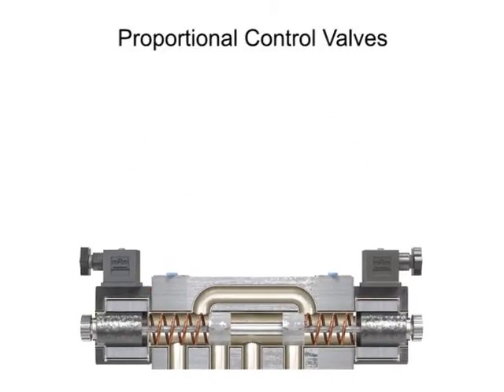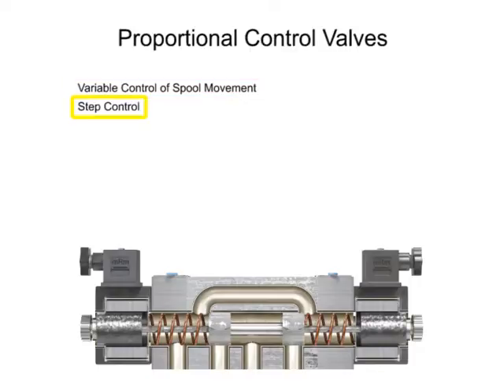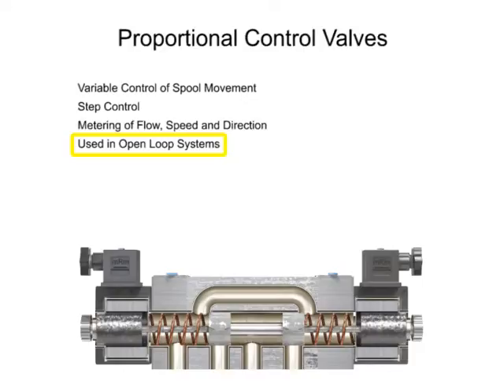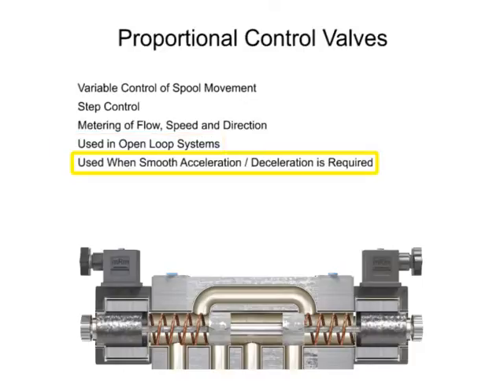Proportional control valves allow for variable control of spool movement, which allows more precise control and metering of flow, speed, and direction. Most valves of this design are used in open-loop systems to smoothly accelerate and/or decelerate an actuator or cylinder.